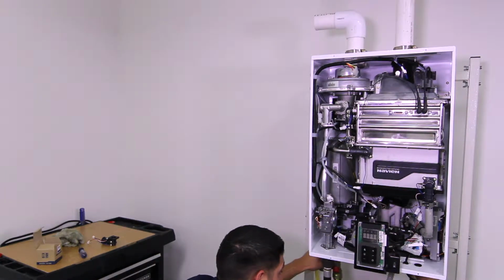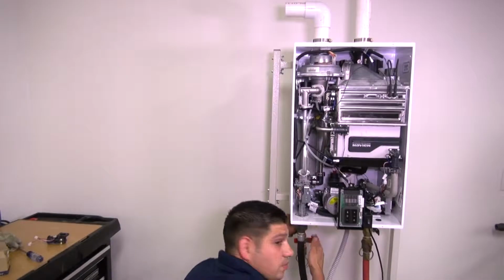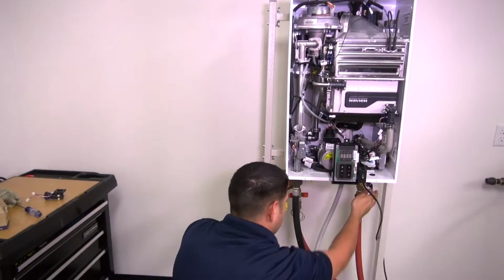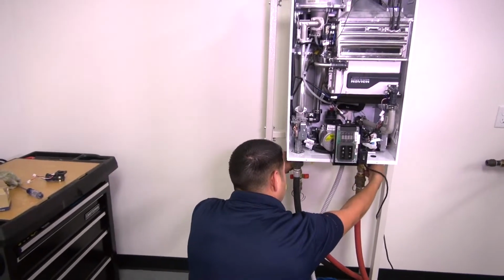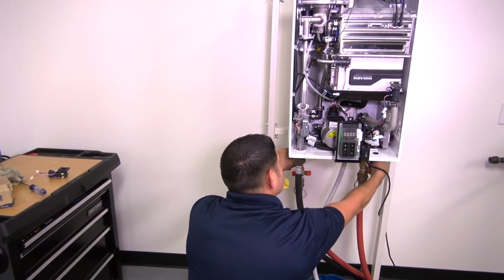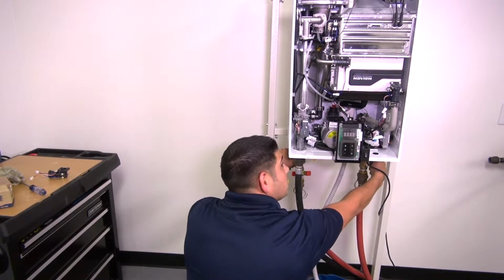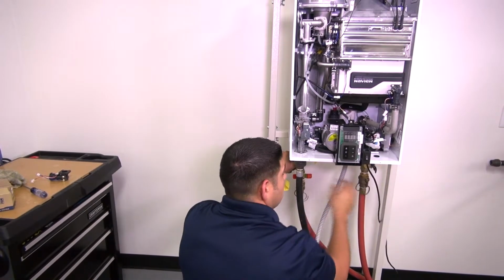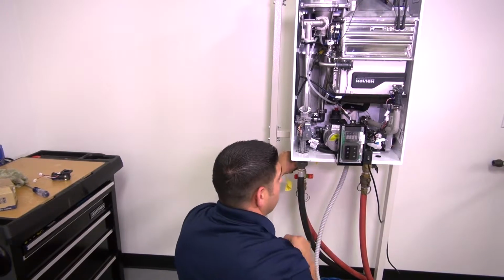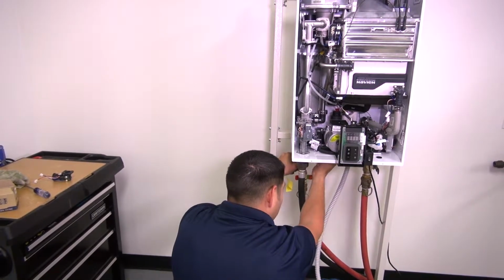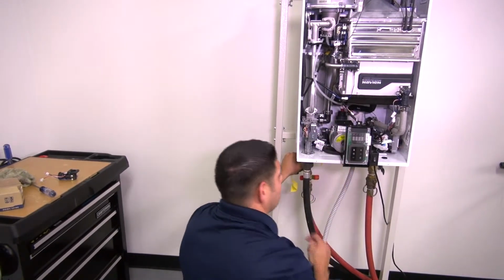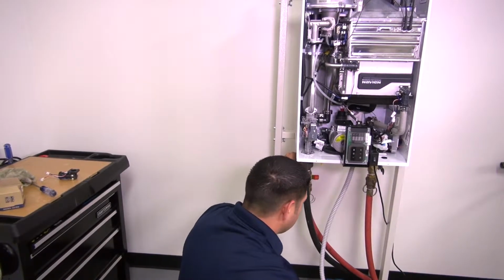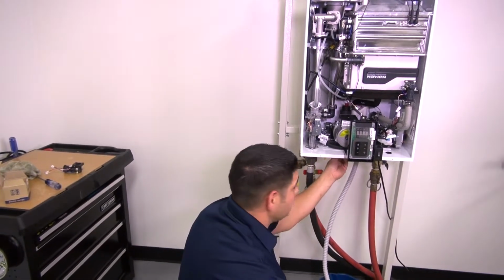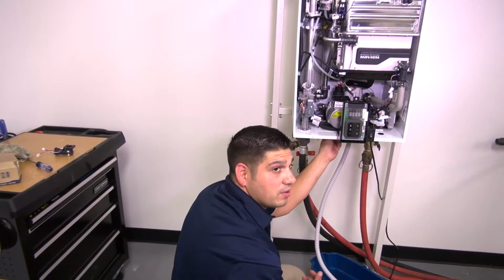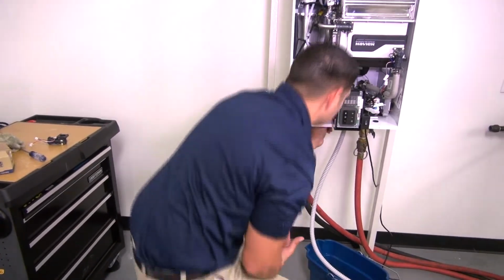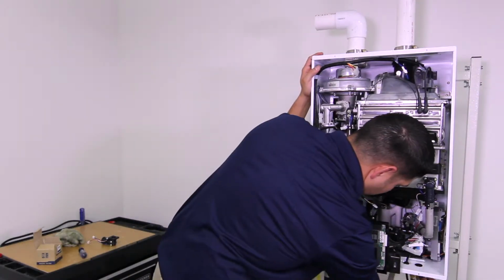So we're going to close off the hot, making sure that the water stays only inside here, and slowly crack the cold. So I'm just slowly bringing this unit up to city pressure. You can hear at the moment the air getting bled out of the air water separator on the top of the pump. I did forget to mention that make sure your bleeder underneath the pump is properly closed, otherwise you're going to start spilling water out as you reestablish pressure.